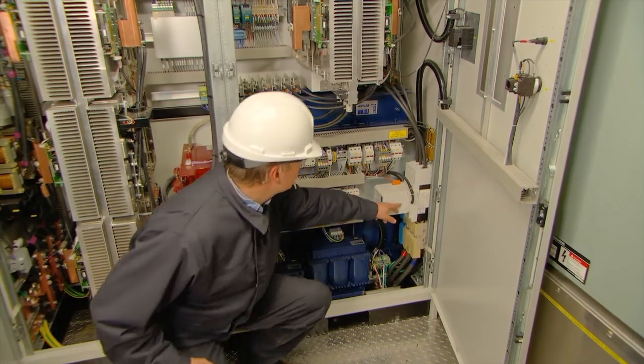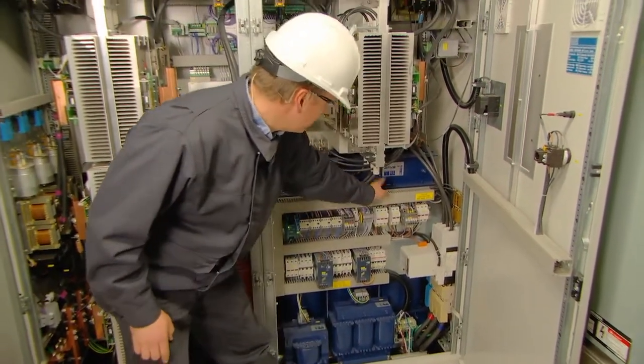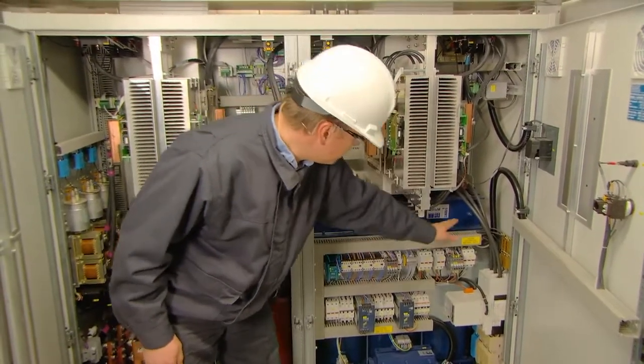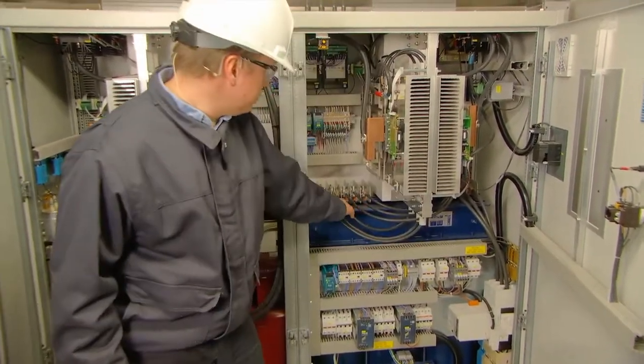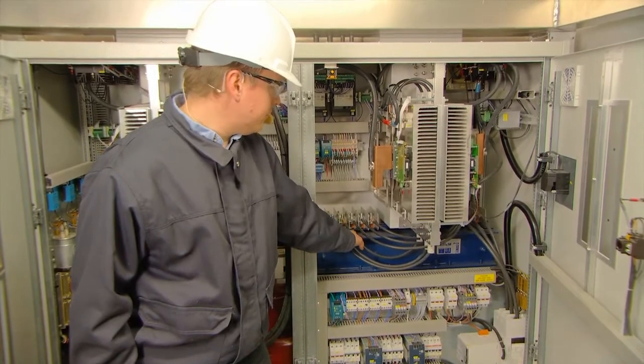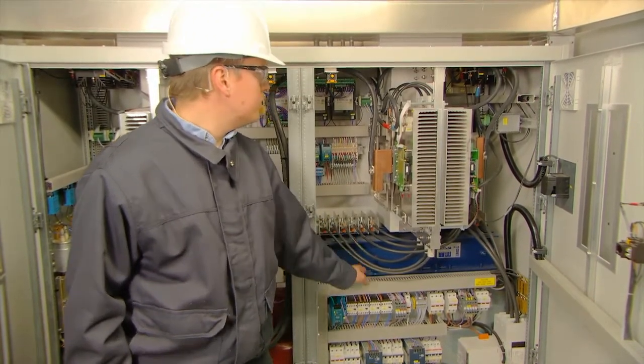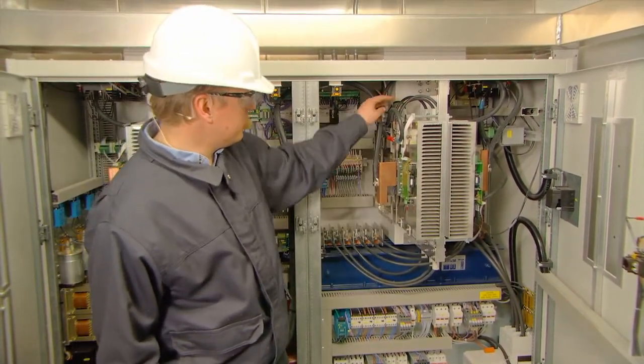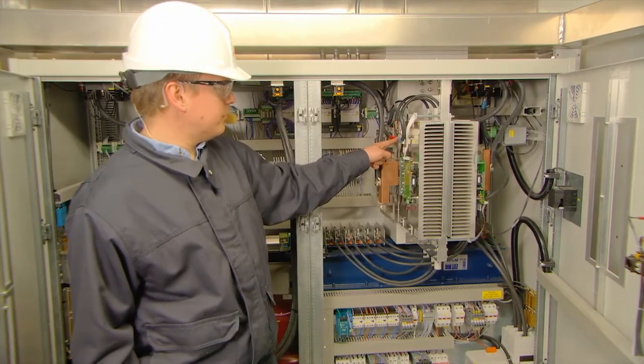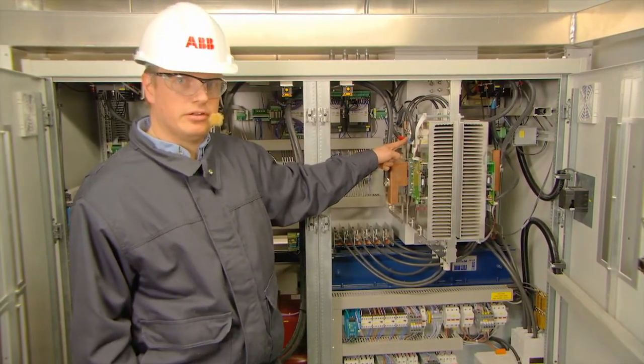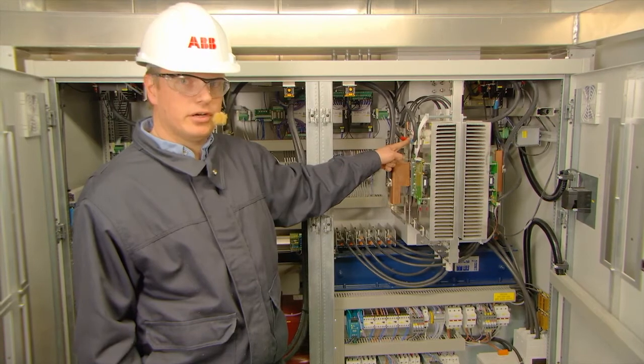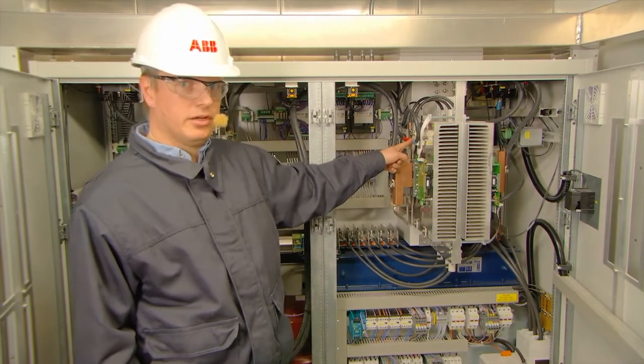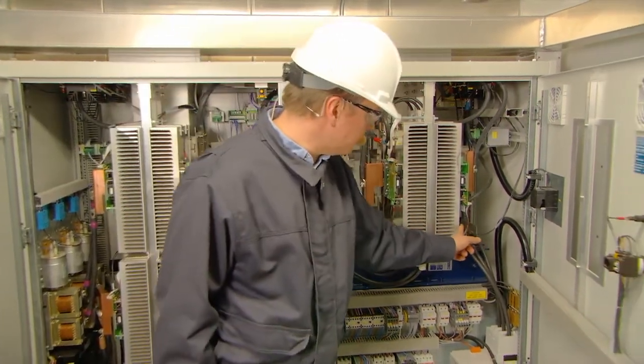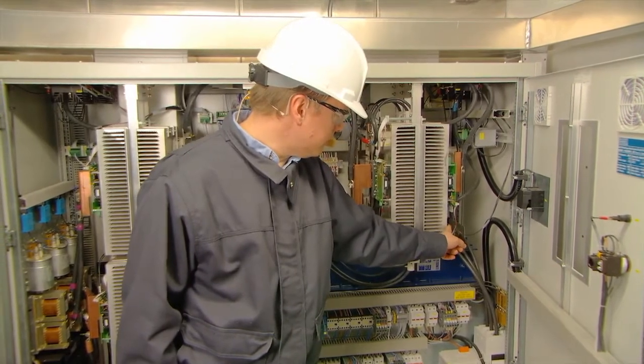The cable from the main contactor goes over the blue transformer, input on the right side, output on the left side. This blue transformer is then coming up over 2 rectifiers. This rectifier is the one generating the DC link. There are 2 rectifiers in parallel, one on this side here, and the second one on the back side of this cooling flange.